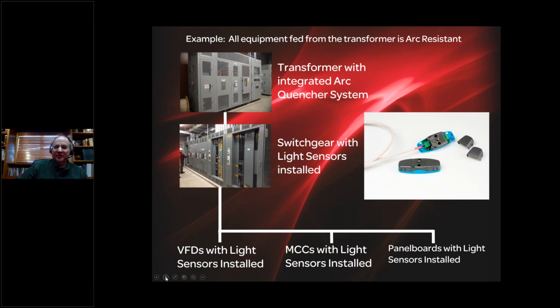There is a picture of the point light sensors, both assembled and with the covers removed, so you could see the wiring that takes place. The particular system that we highlight here today accepts both point light sensors and fiber light sensors, and it's quite common for us to use both types of sensors in the same installation. The wire you're looking at is a common Belden 18 gauge wire.